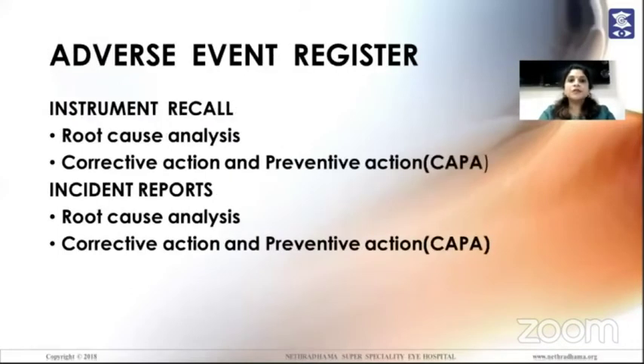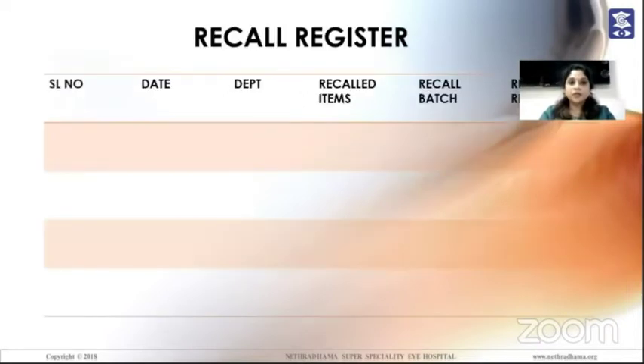Coming to the adverse event register, this has to be maintained in the OT, which should include instrument recall, where a root cause analysis of the recall is done, and corrective and preventive action is documented. And the incident reports—any incident that has happened in the OT—require root cause analysis and corrective preventive action to be done. So this is the format of the recall register.